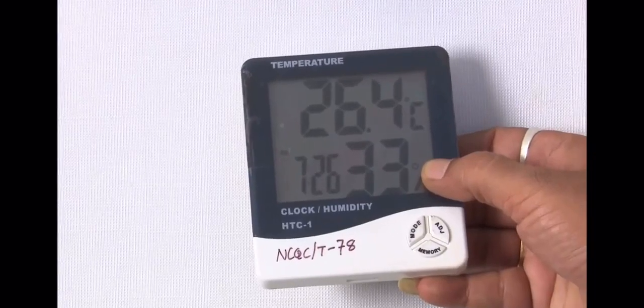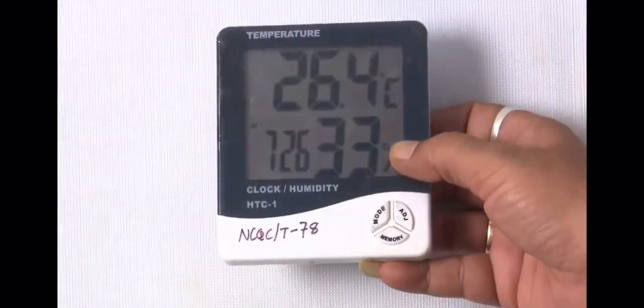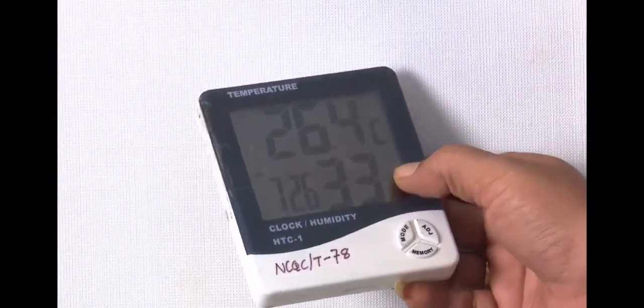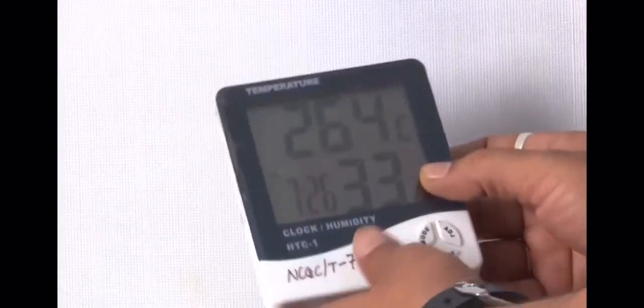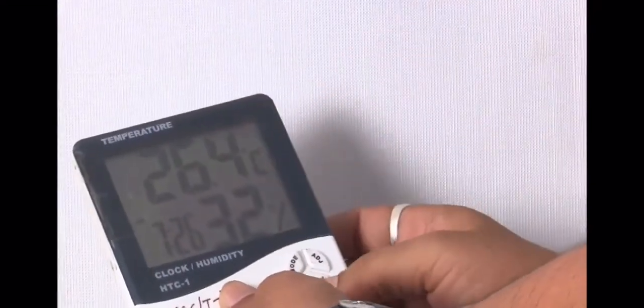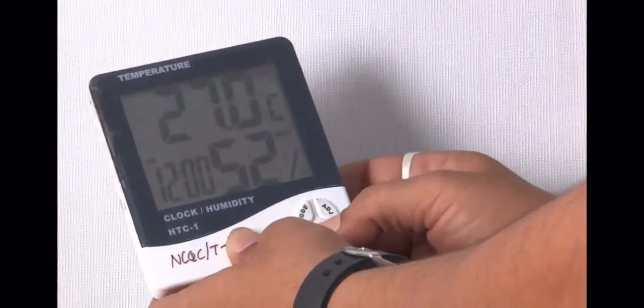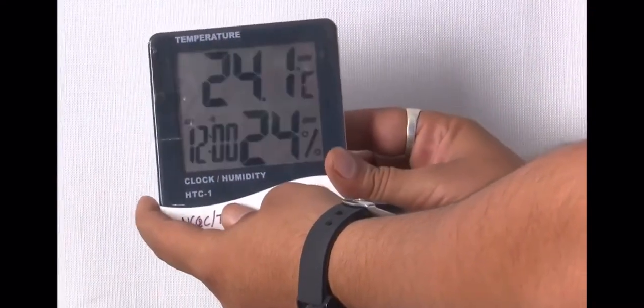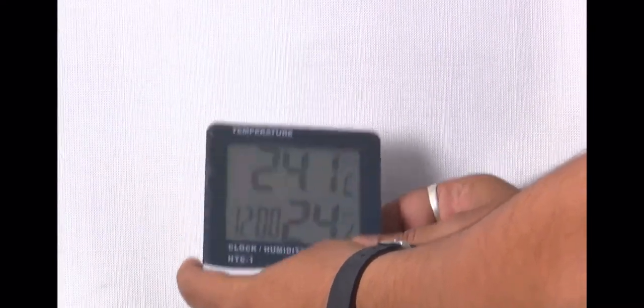Here I am demonstrating live display of step-by-step calibration method for digital thermohygrometer. After cleaning, visually inspect the digital thermohygrometer, meaning UUC, for any physical damages, missing parts, etc. Also check that its display is working properly.